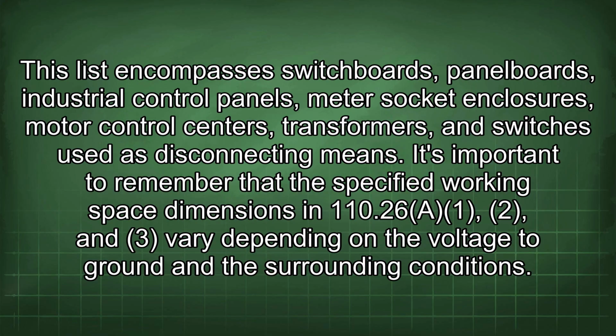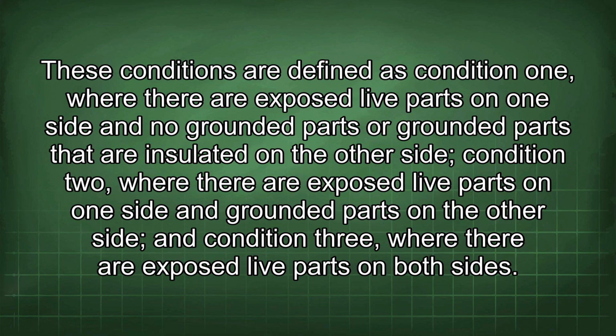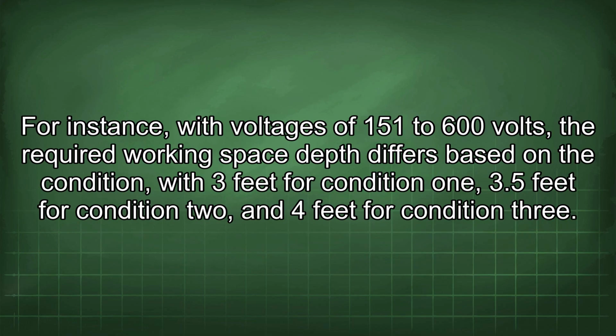It's important to remember that the specified working space dimensions in 110.26(A)(1), (2), and (3) vary depending on the voltage to ground and the surrounding conditions. These conditions are defined as Condition 1, where there are exposed live parts on one side and no grounded parts, or grounded parts that are insulated, on the other side. Condition 2, where there are exposed live parts on one side and grounded parts on the other side. And Condition 3, where there are exposed live parts on both sides. For instance, with voltages of 151 to 600 volts, the required working space depth differs based on the condition, with 3 feet for Condition 1, 3.5 feet for Condition 2, and 4 feet for Condition 3.